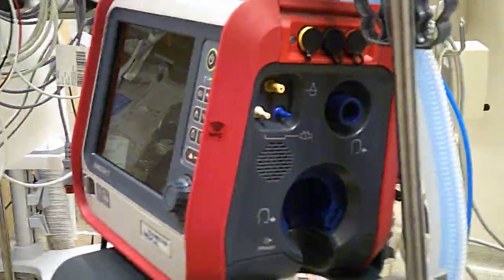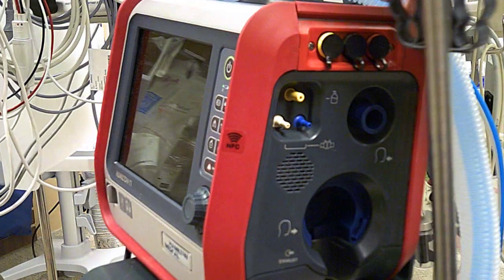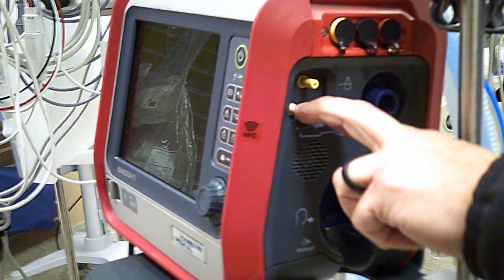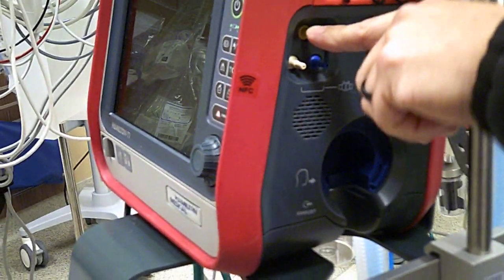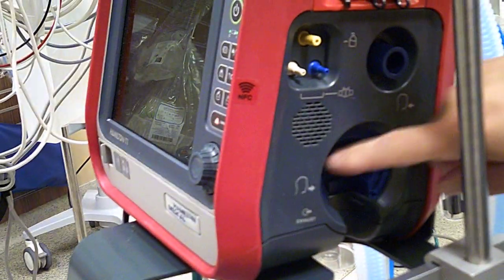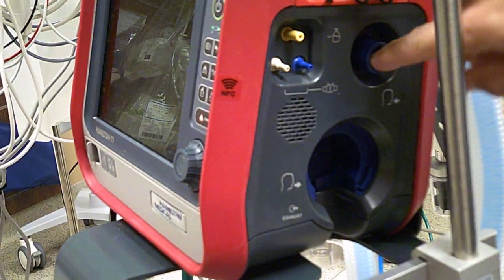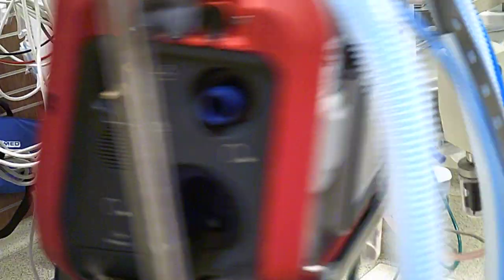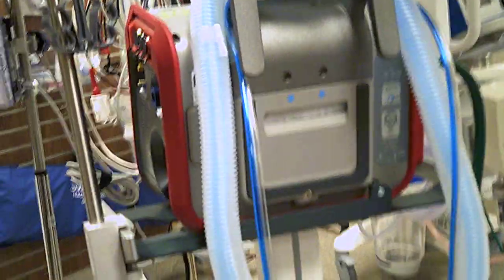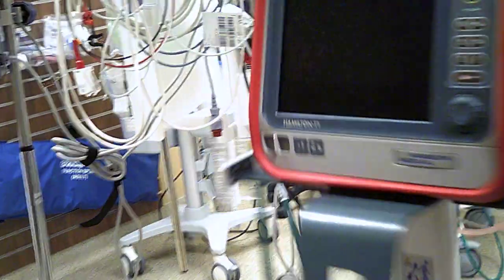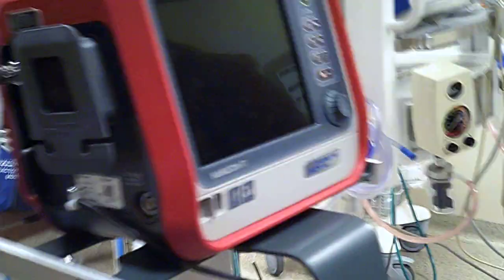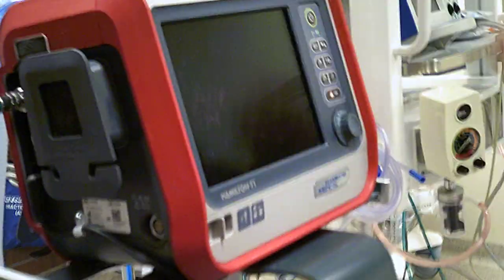On this side, we're not going to use any of these, right? Nope. So this is where our transducer lines would go. And I said before, our neb oxygen line would go here. This would be our exhalation port and our inhalation port. I think that's pretty much it. Filter for the back, which Bio should be replacing. Oxygen and your power. If you guys are getting a leak, make sure this is tight because they do come loose. Put it on that one. Okay.